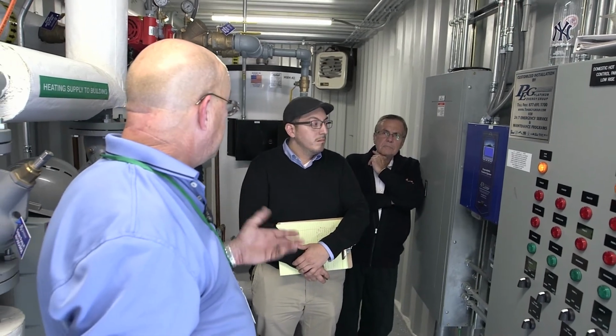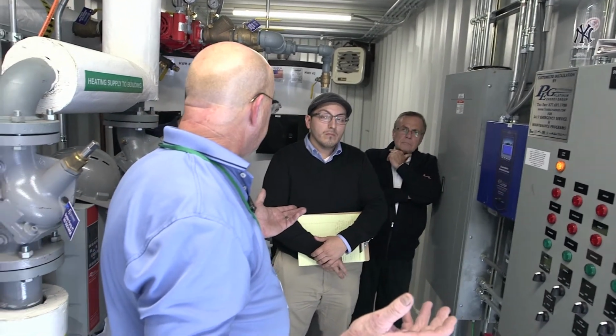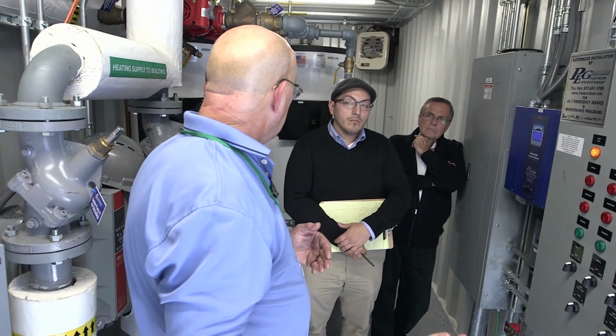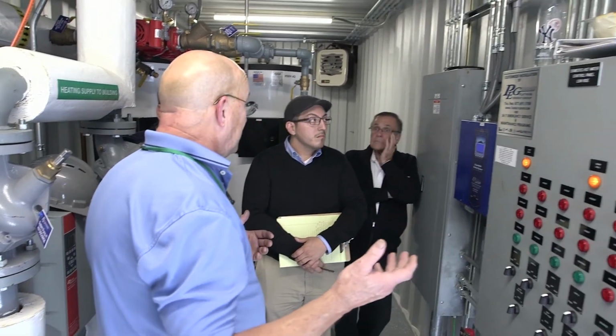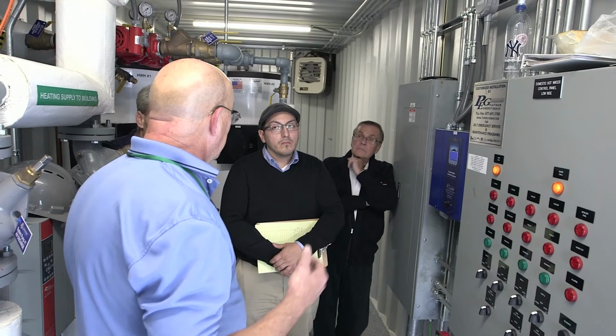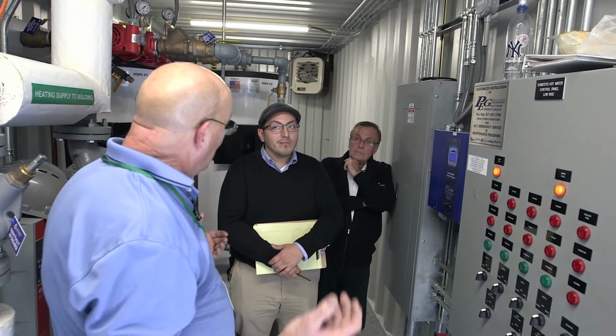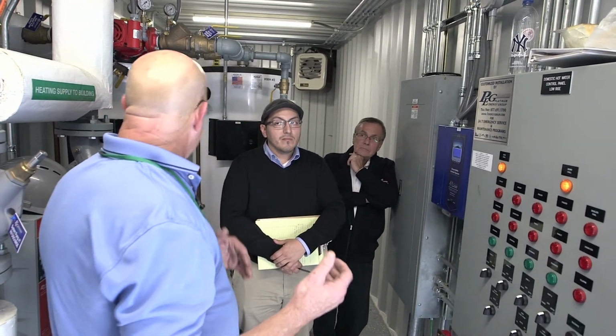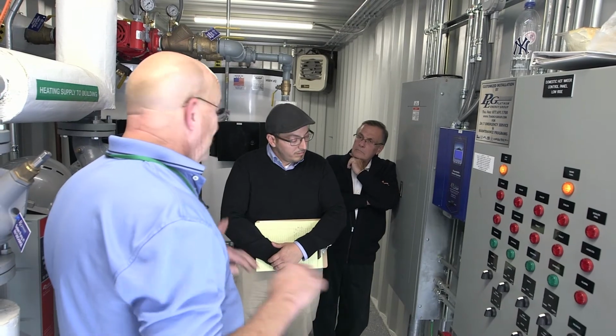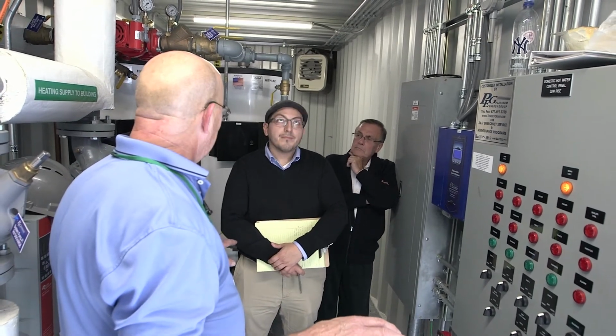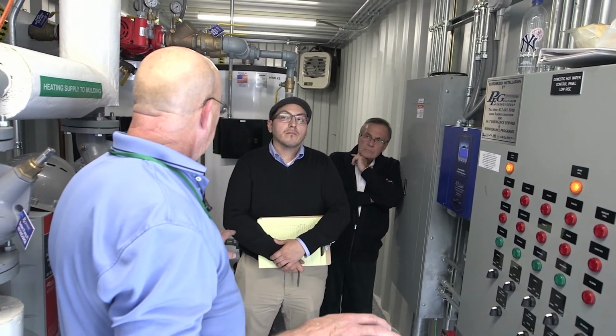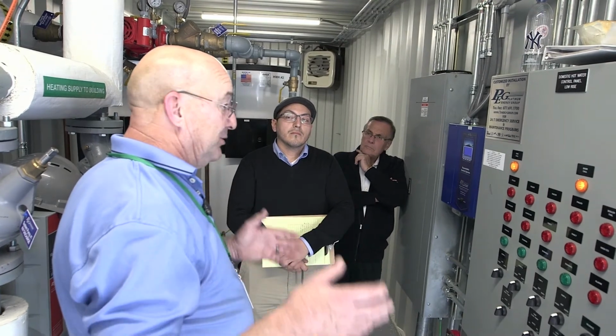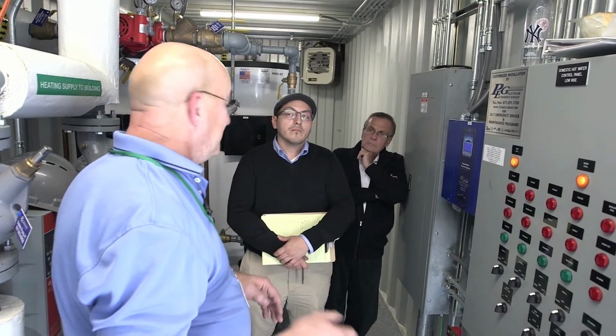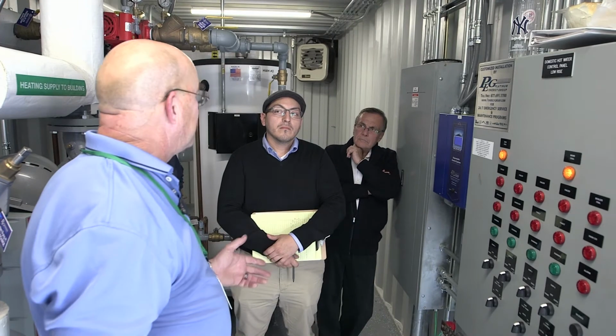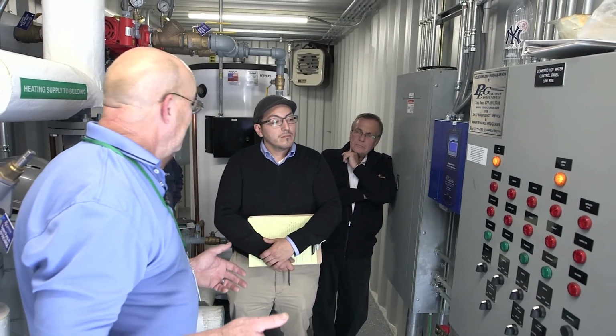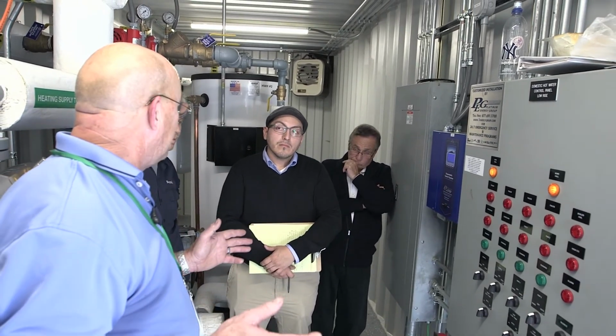It's going to email whoever if there's a failure, if the boiler goes down. It's not anymore, oh, I have no heat, and the super's got to run up to the top and say, oh, the boiler's not on. You should know that long before the people are cold, because you're going to get an alert. Okay, the water's too cold. Something's going on. You've got to go check out the boiler. That's the nicest part of that.